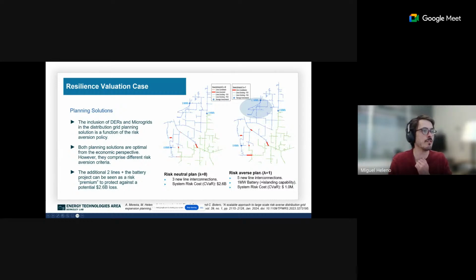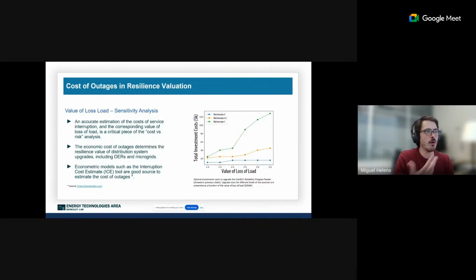If you go for a fully risk-averse plan with lambda equal to 1, not only are the 5 lines selected as the optimal solution, but a 1.1 megawatt-hour battery is also placed in this area of the grid. So your risk aversion drives the decision, and the worst-case system cost drops to 1.0 million. By increasing risk aversion, you decrease the system's exposure to catastrophic events — of course this depends on how much you value loss of load, and here's a sensitivity analysis around it.